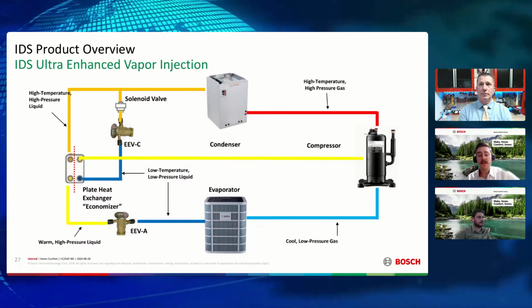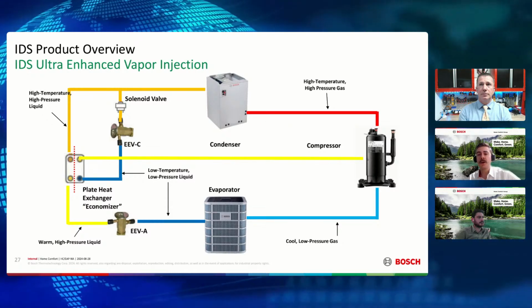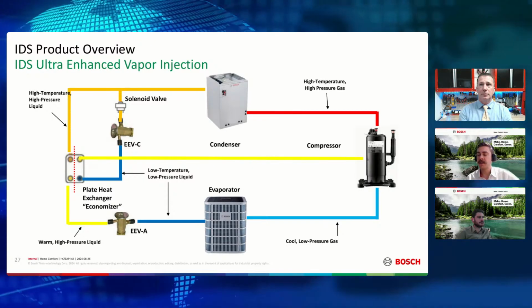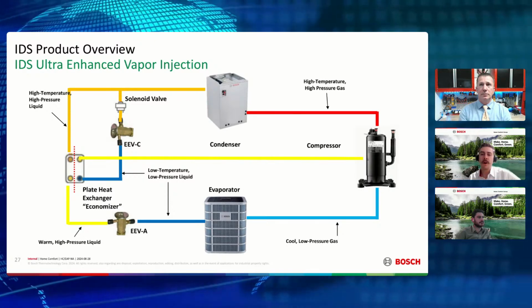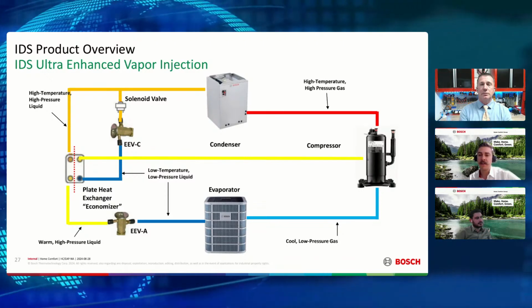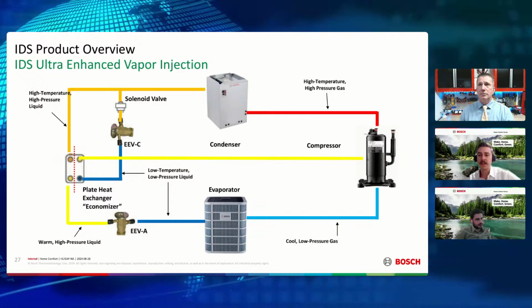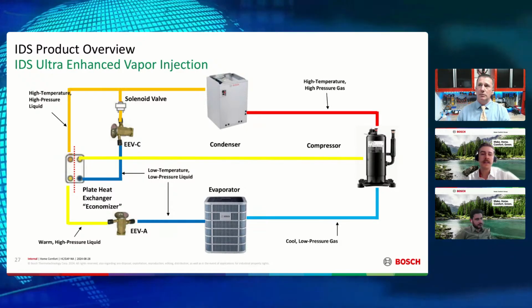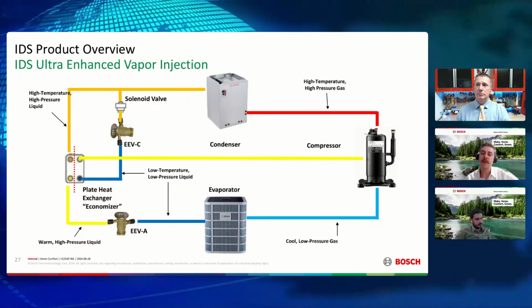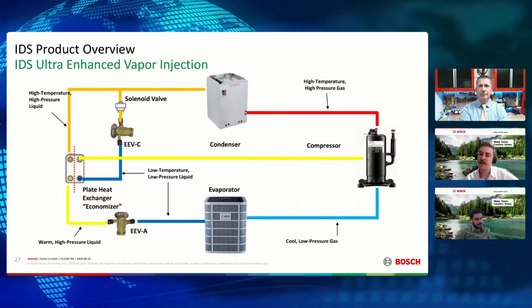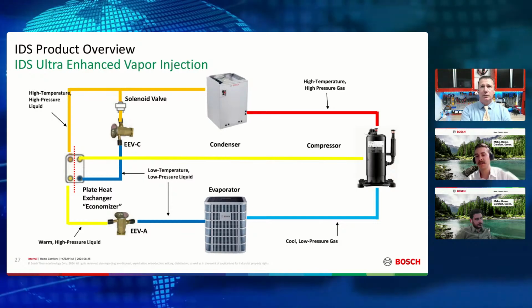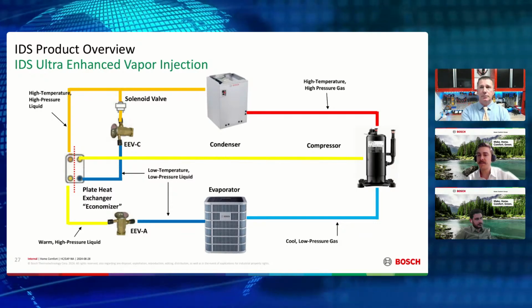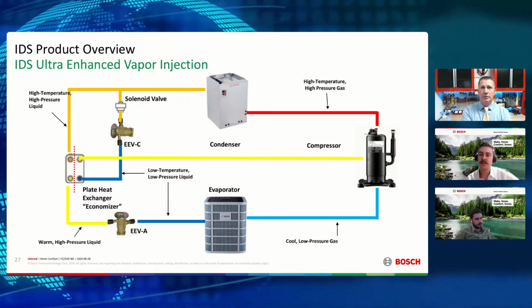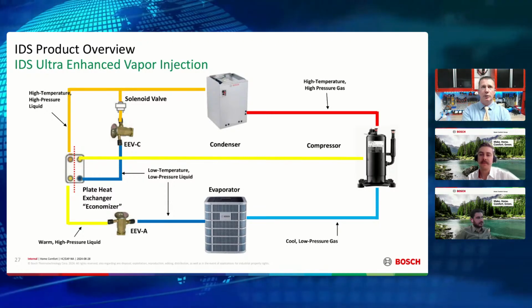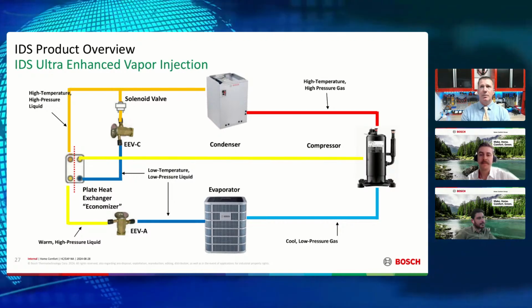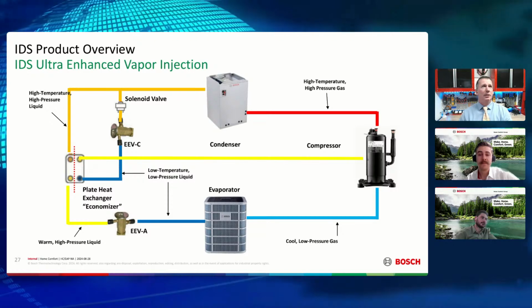Yeah, but there is a slight added benefit of starting to run that earlier, even at slightly moderate temperatures. Our system actually starts to open that solenoid valve between 50 degrees and 40 degrees. Part of the reason is that you can absorb more heat, so your compressor doesn't have to work as hard for the same capacity. You can decrease the compressor speed, which saves energy and also helps reduce noise. And then we're bringing some cooling back to the compressor, so we're maximizing the life of the compressor.